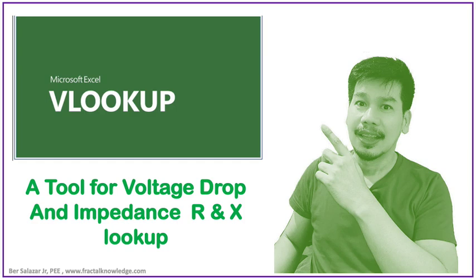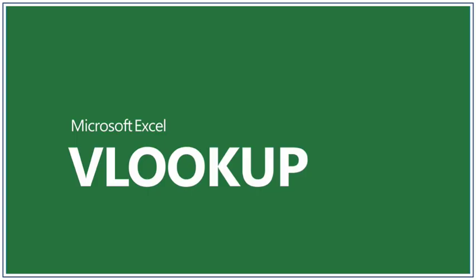In this step, I would like to share with you some Excel techniques to make our job easy with regards to voltage drop. We will be needing the Excel tool called VLOOKUP. If you have lots of load schedule, looking for the value of resistance and reactance in the table is tedious. Excel will help us to make the calculation easy and faster, and finding a value is a lot easier.